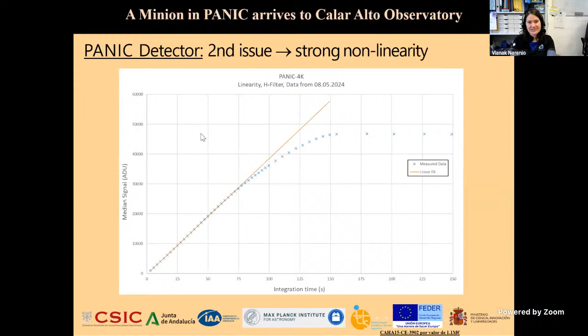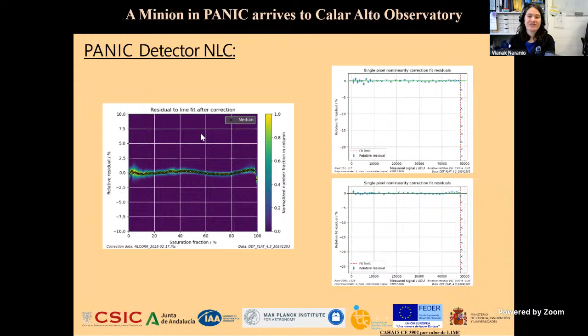So please, next slide. A fellow of ours is working on a non-linearity correction. Results will for sure be available not later than May. And we see that after the correction, we have very low residuals, less than 1%. And you see from different pixels, which he picks as a sample, that the results are also similar. I won't get into details, but it is one of the common approaches: an exponential function and a polynomial correction, in this case of the fifth order, for reducing the residuals in this way. Okay, next slide. And well, that was all from my side. If you have more questions regarding the detector, you can contact me offline.